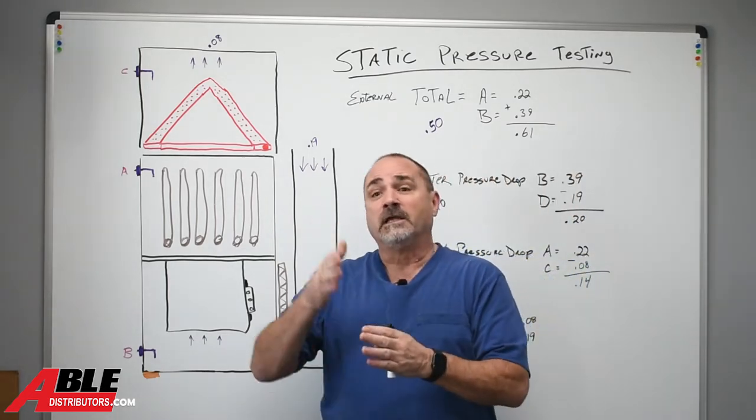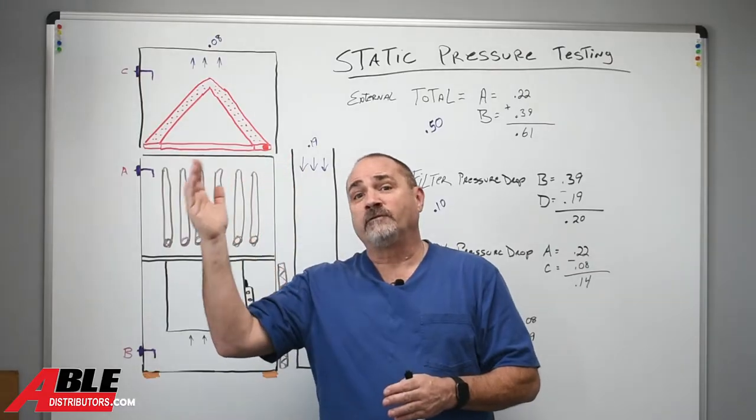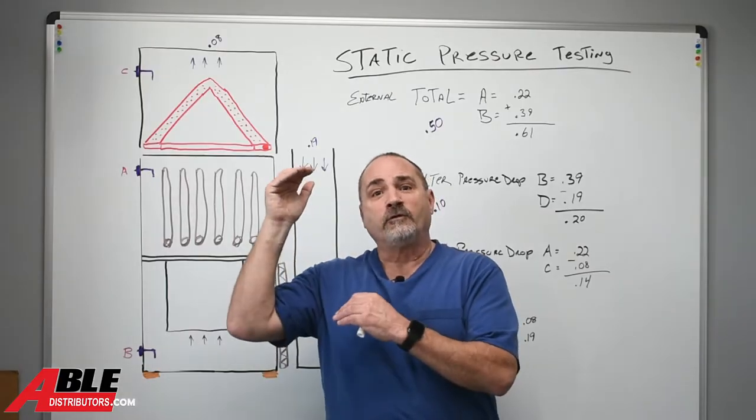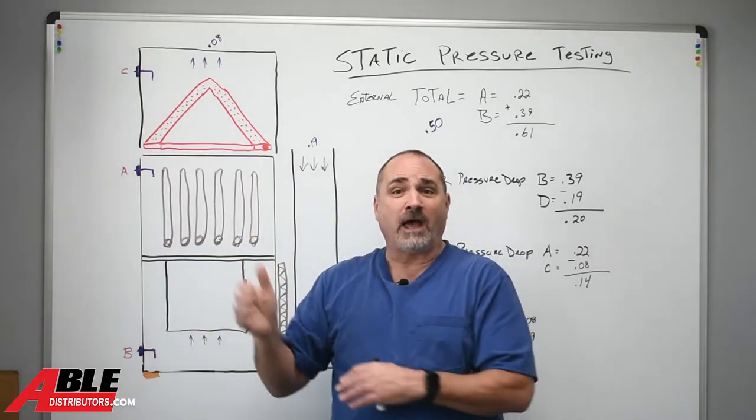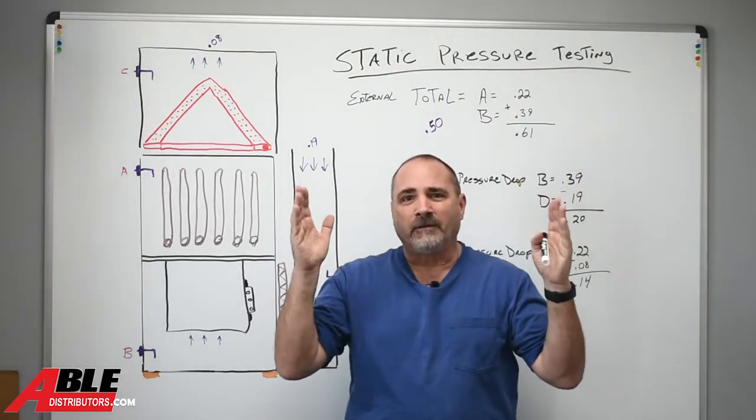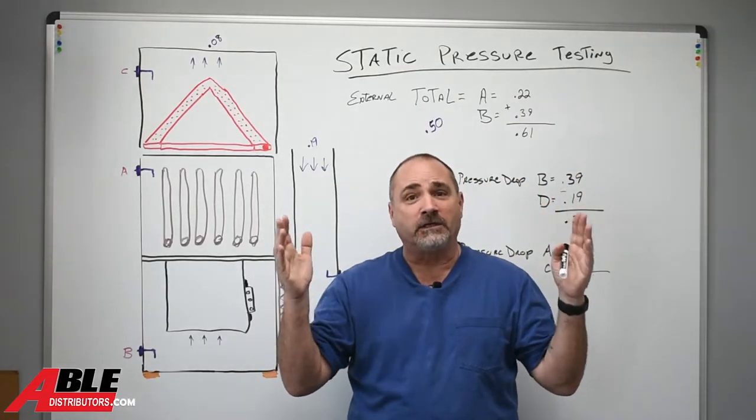You can literally go from a 0.50 external static pressure, and by external it's everything outside the furnace. When you go from a 0.5 to a 1.0, that little bit of difference honestly is not that hard to achieve. A few mistakes in that duct work and you're going to hit it.